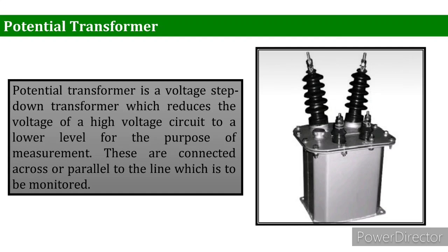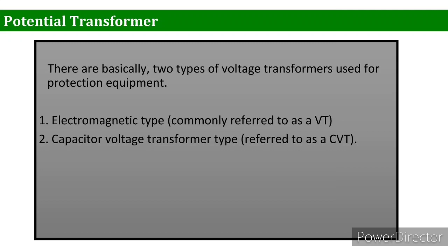Potential transformers can be single phase or three phase. Irrespective of the primary voltage rating, they are designed to have a secondary output voltage of 110 volts. There are basically two types of potential transformer used for protection equipment: the first is the electromagnetic type, commonly referred to as VT, and the second is the capacitor voltage transformer type, referred to as CVT.